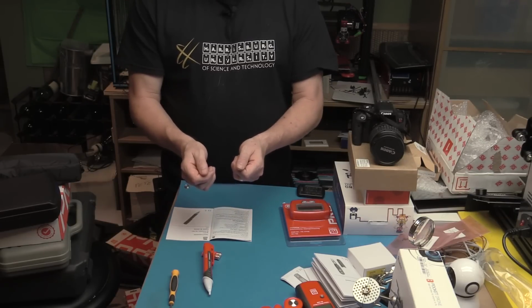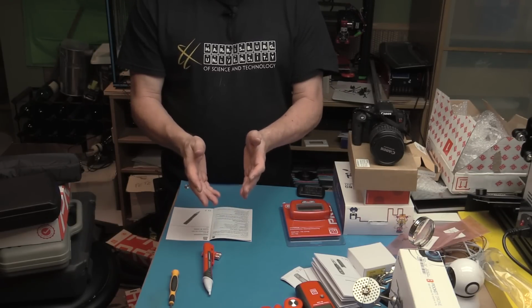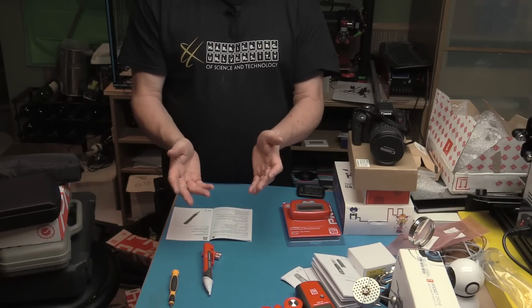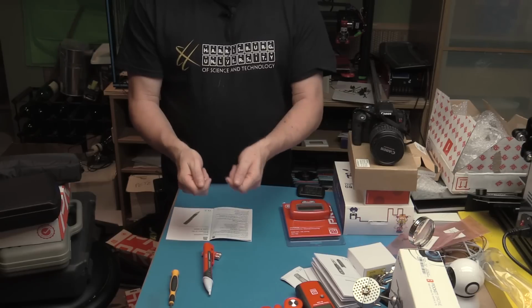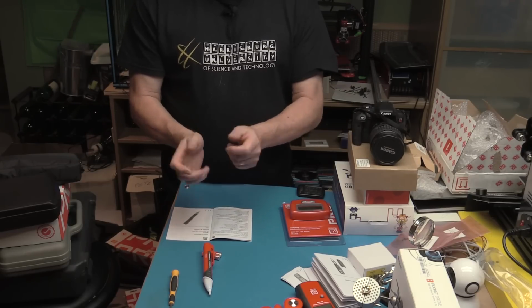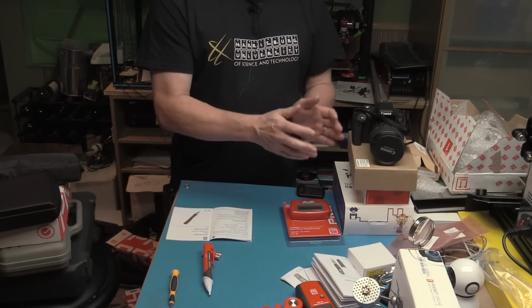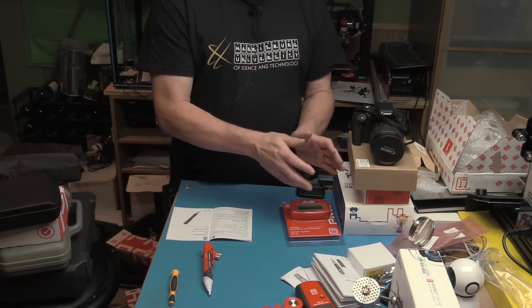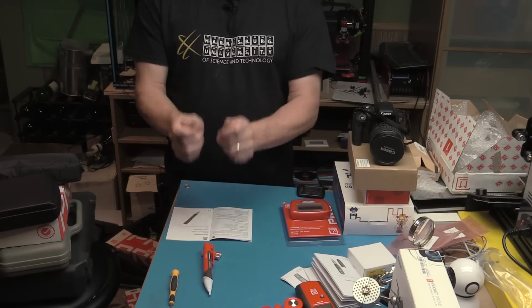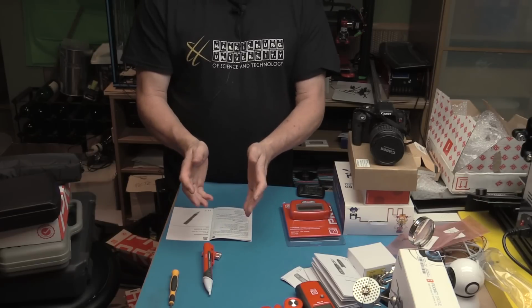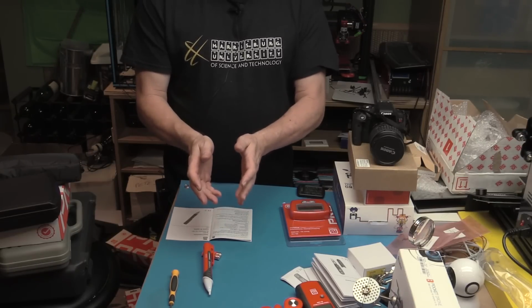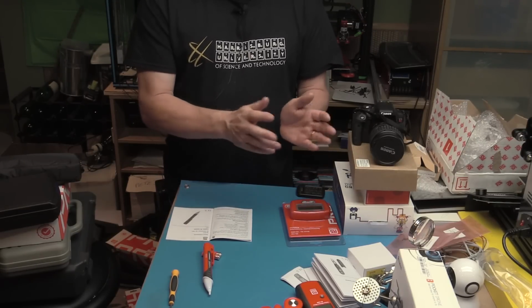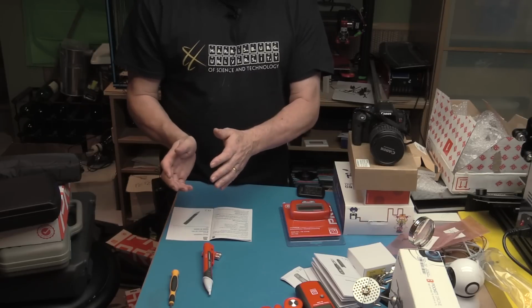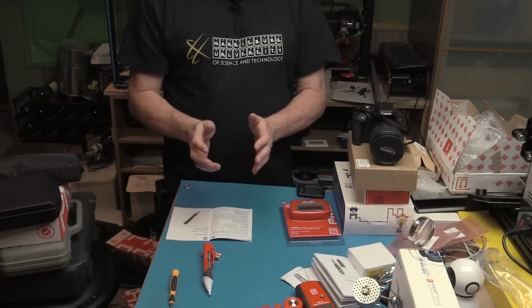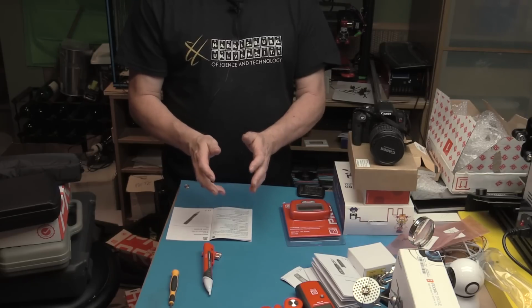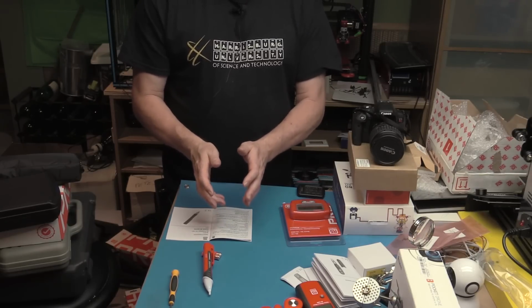And if you get what you expect, so for instance, you're measuring for 0 volts because you've powered down a 3-phase circuit, verify that you've got the 0 volts, but then when you've done that, go back and retest your meter to make sure it is still working. Because you never know, when you connected it onto those things, you might have fried something depending on what real voltages are there. So you do this double check just before you start and just after you finish to make sure your meter is working properly. And that's the only way to ensure you're not going to kill yourself, basically.